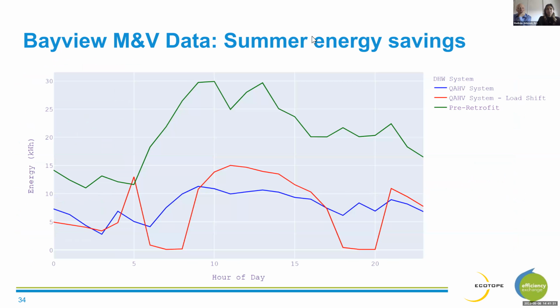And so this is an hourly energy use profile at Bayview, and it kind of shows 2 of Ecotope's guiding principles in action. Number 1 is that efficiency is energy. So if we compare the green electric pre-retrofit electric resistance usage to the blue post QAHV install, you can see that the QAHV is much more efficient, and it uses less energy during every hour of the day. And then the second guiding principle in action here is that when matters. So we have 2 peak periods, one in the morning and one in the evening, where we've been able to shift most of the energy outside of these peak periods, and you can see that in the red line. We've pushed that energy outside those peak demand periods.